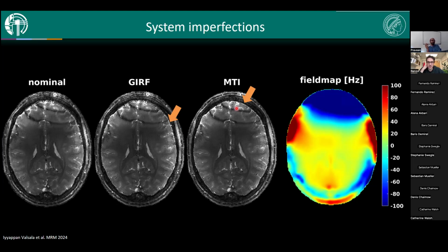Okay, makes sense. So you showed scope trajectories, but you're not really using them in your recon, right? Only to calibrate the GIRF. Yeah, exactly. The problem is the scope also has an acquisition duty cycle limit. We are repeating at a much faster pace, with a 10 millisecond interval excitation, so you can't measure the entire trajectory.